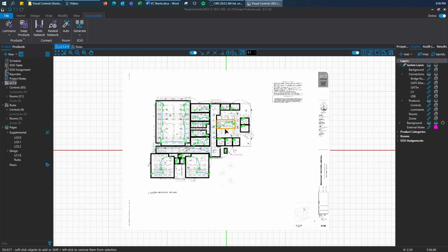To swap from nLight wired to nLight AIR, we need to make sure all of our devices are wired with Cat5 before swapping. To swap from nLight AIR to nLight wired, we need to make sure rooms are drawn before swapping. Assigning SOO rules to your rooms will yield more accurate results. Lastly, always perform a thorough quality check after a swap is made to ensure the right devices were imported during the swap and that sensor placement is accurate for your layout.